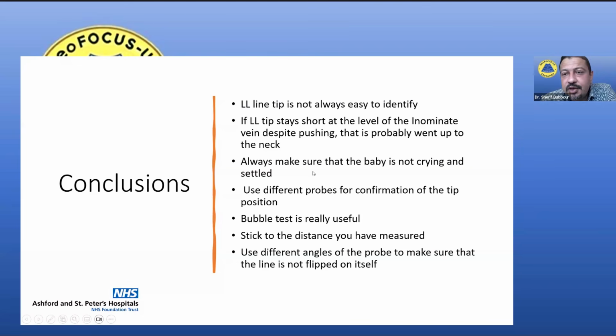Always make sure that the baby is not crying and settled, because if the baby is moving or crying, that might give you false impressions about the length of the line and make it more difficult to identify the tip. Using different probes, we found very useful in our practice. We are not only using one probe, we are using different probes to identify the tip position. The bubble test, I found really useful. When you focus or reduce the depth, you can identify the bubbles coming when you are pushing the saline.